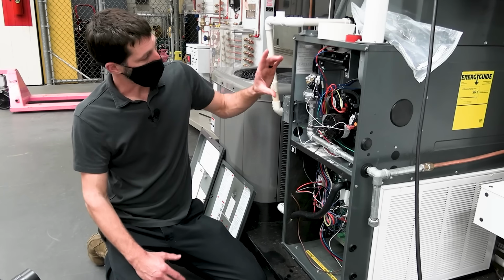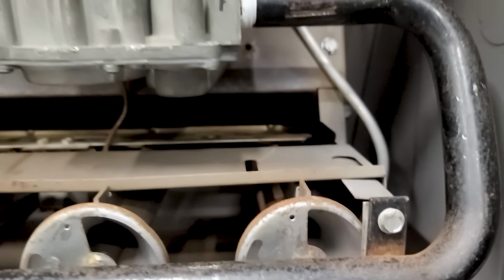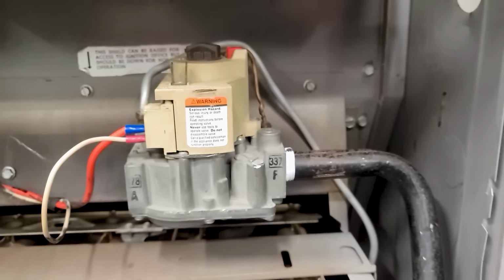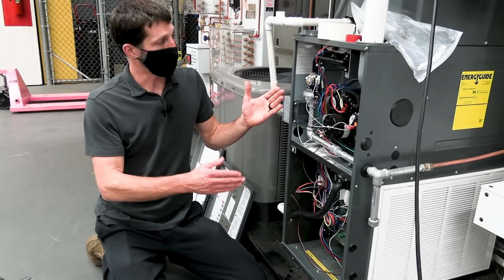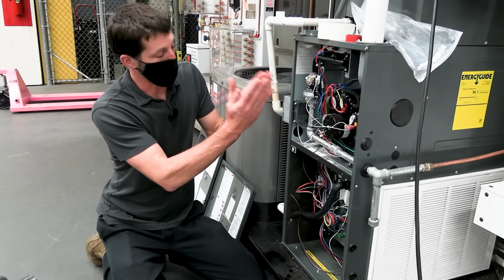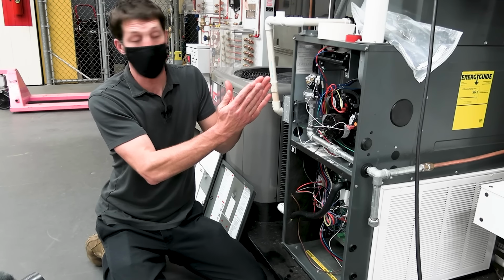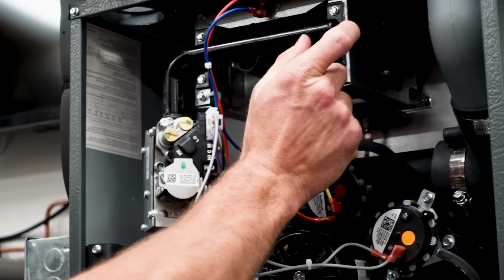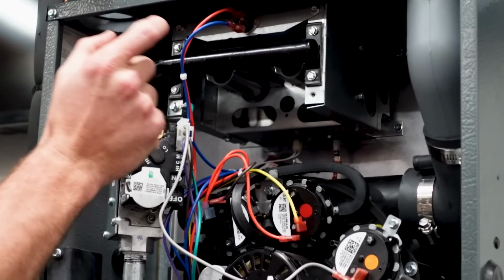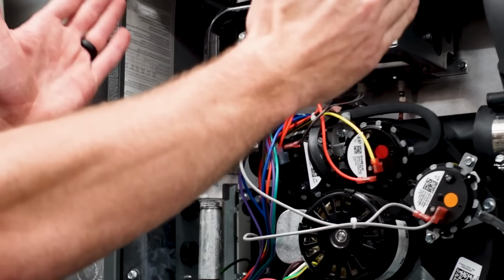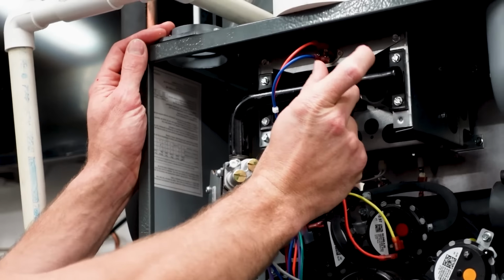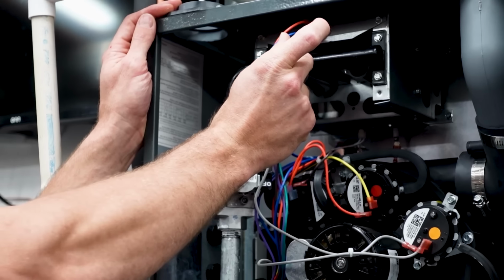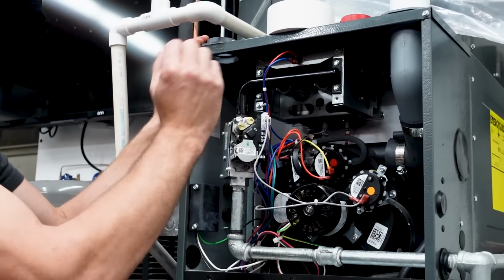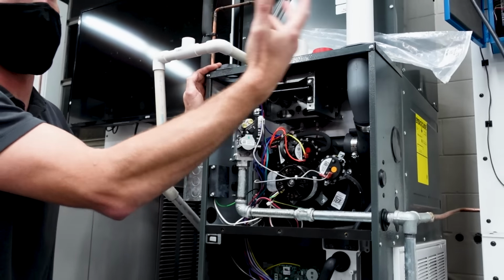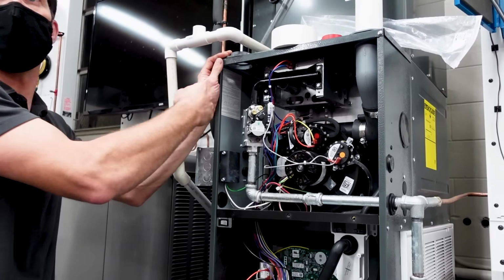All that to say, this is a direct ignition gas valve, and if you ever see a small 1/4-inch aluminum tube coming off of this gas valve, that's called a pilot ignition. It ignites this little tiny pilot, and there may be flame rectification that occurs on this little pilot, but guess what? It's only on one side, so if you have 4 or 5 burners, it's only really checking for flame rectification in one spot. Whereas with direct ignition, you have the hot surface igniter on one side, or spark ignition, and you have the flame rod on the other side.